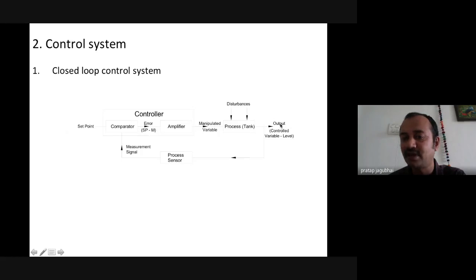Let's take an example of drum level, where the drum level is sensed by the transmitter, and the comparator takes the error signal from the set point, which is entered through the keypad. This error signal goes through the controller, where it is conditioned, and is given to the control valve, so that the control valve takes action to maintain the level at the desired position. Control valve opening or closing will give water inside the boiler, and the level will be maintained. In this way the level can be controlled, and so there is a closed loop action.